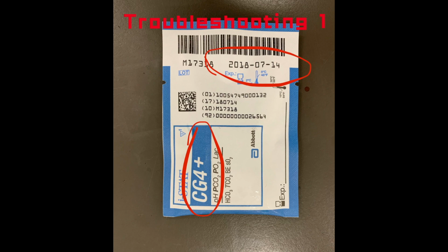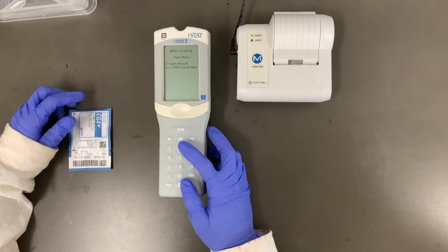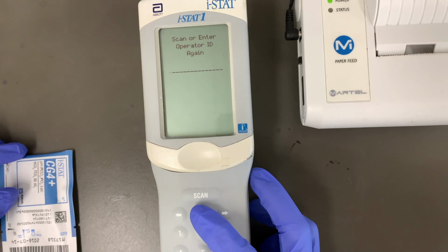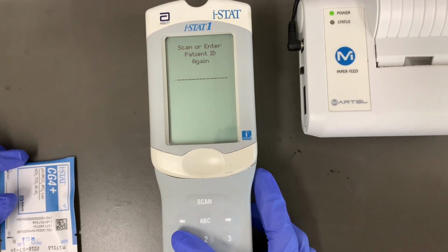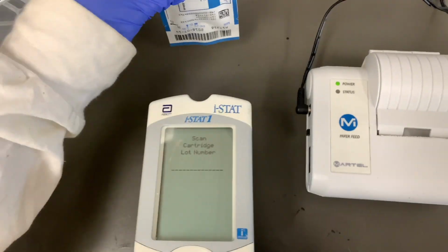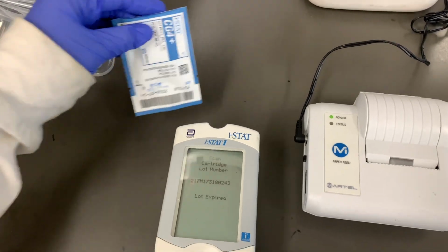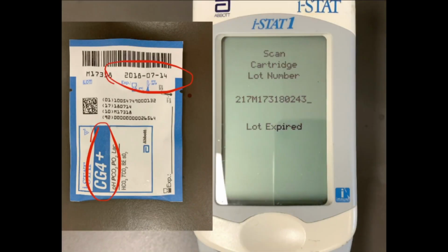For the next part of the demonstration, we will show you how to troubleshoot a couple of common errors. In this case, the cartridge lot number has expired. Now if you attempt to scan the cartridge lot number, the screen will display lot expired. Although it is a simple correction, this emphasizes the importance of checking minor details before testing.